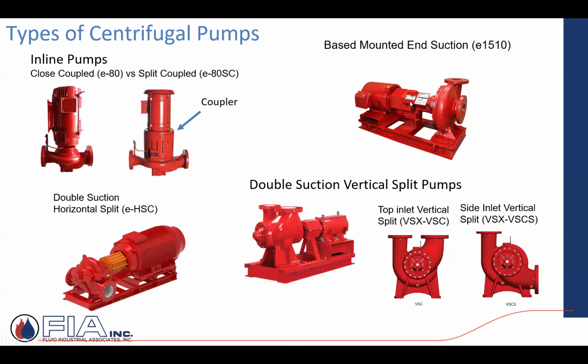Moving to the right here with this arrow pointing, instead of inline, now I'm getting to what they refer to as a base-mounted end suction pump. And so end suction, all it means is I'm sitting on a base, the inlet is the end of the pump, the end suction, and then I have a top discharge coming up the top here. As you get into larger capacities, from a service standpoint, from a mechanic working on it, sitting on a floor, there's easy access, whether it be to the motor, the coupler, the bearings, or the seal. It's an easier to service style pump, very common in the industry, with a base that gets grouted. We'll talk a little bit about that later on with some details, but vibration isolation, grouted to the floor through the base.